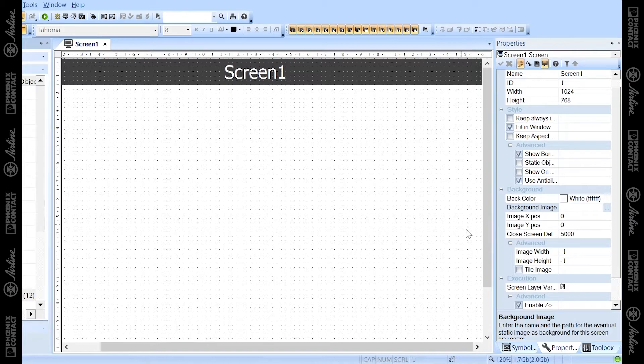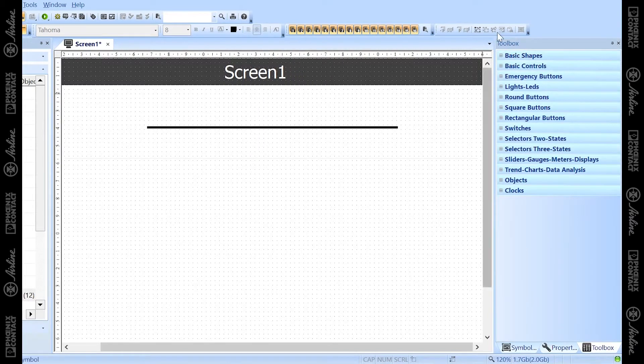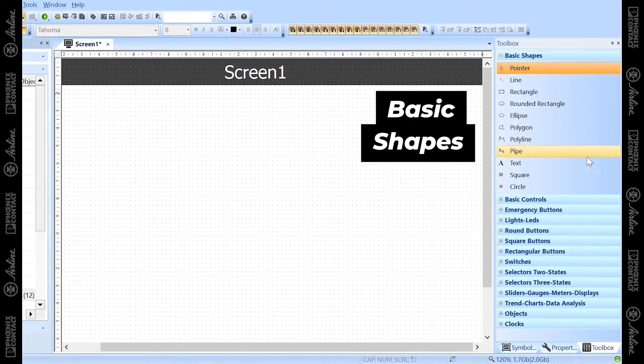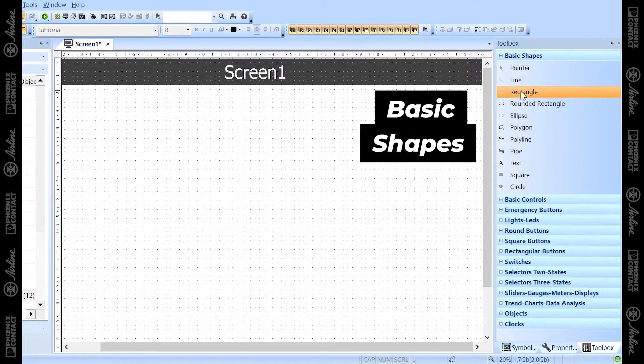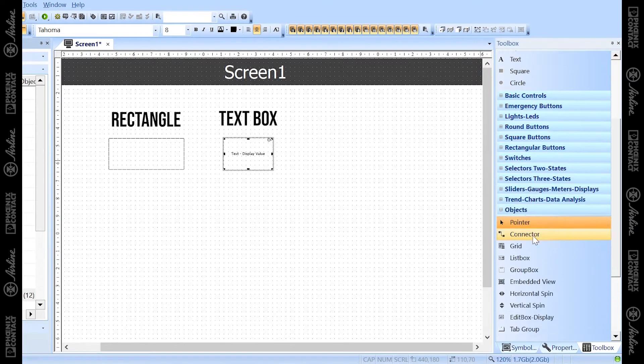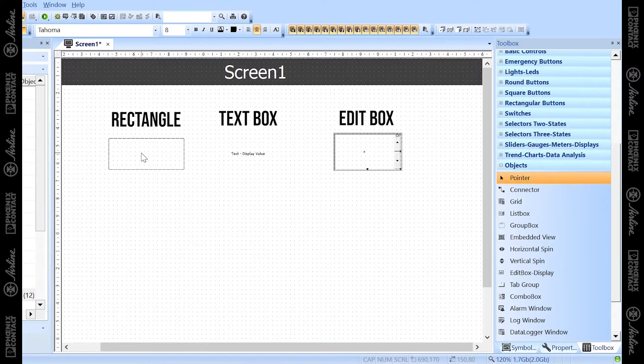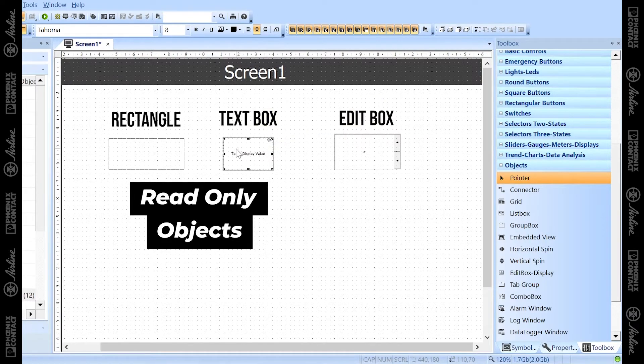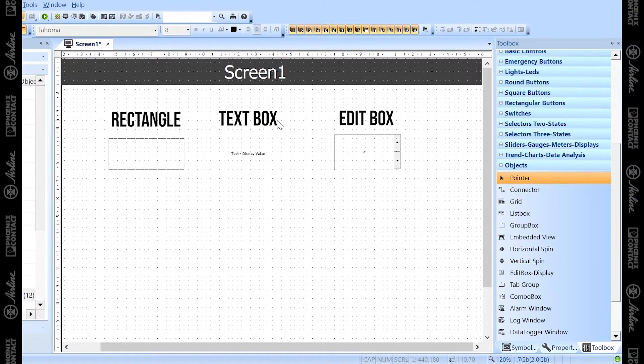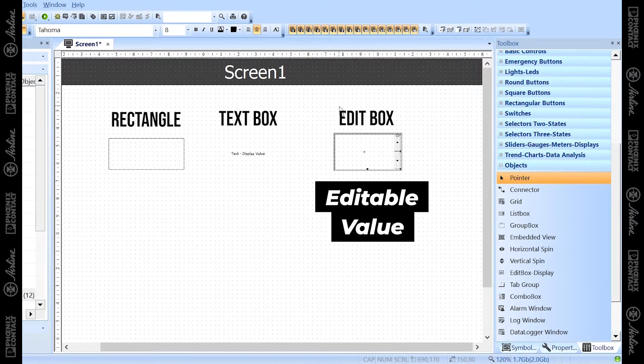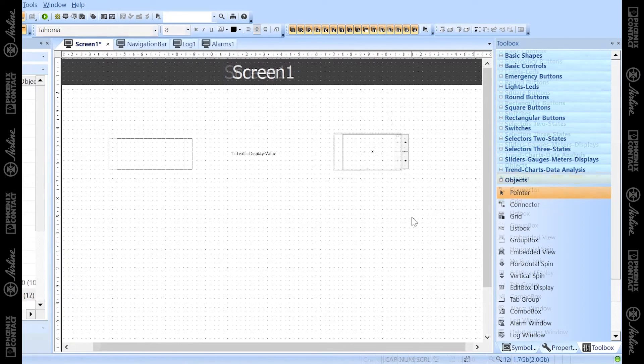Now we're going to start adding objects into our screens from the toolbox. Inside the toolbox you'll find a lot of the shapes and objects you'll be adding as you develop. Under basic shapes you'll find shapes you'd expect. I wanted to distinguish between a rectangle, a text shape, and an edit box. The rectangle and text shape are read-only objects used to display static text or values. The text shape is just a rectangle without borders, while the edit box allows users to input or write values into the screen as it's running.